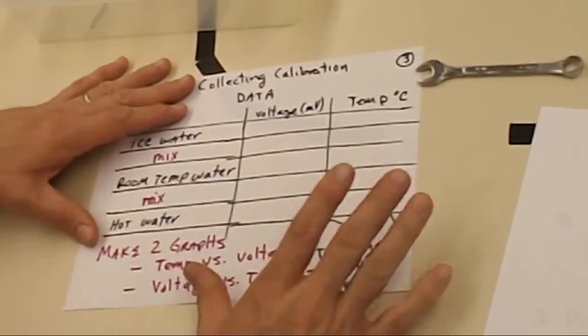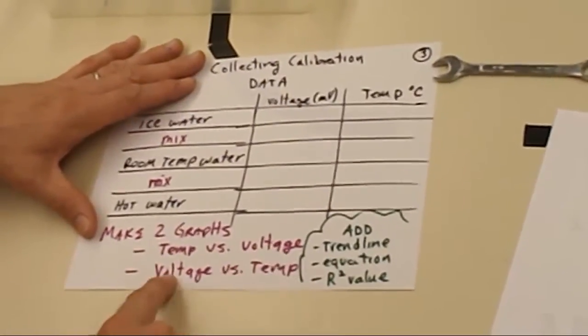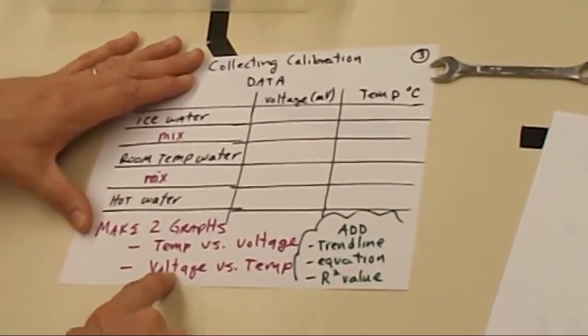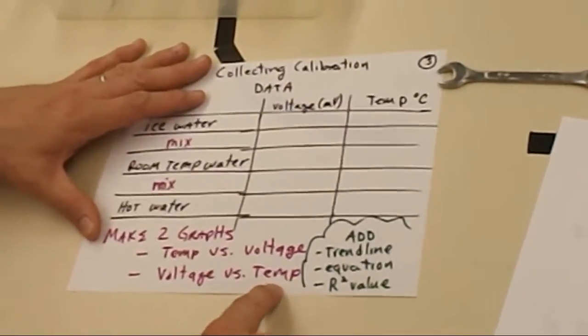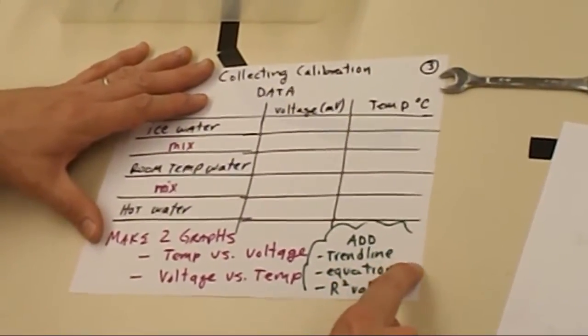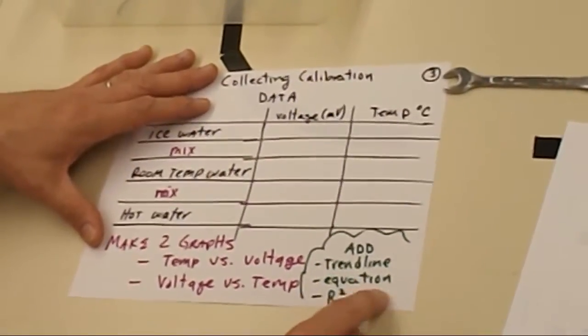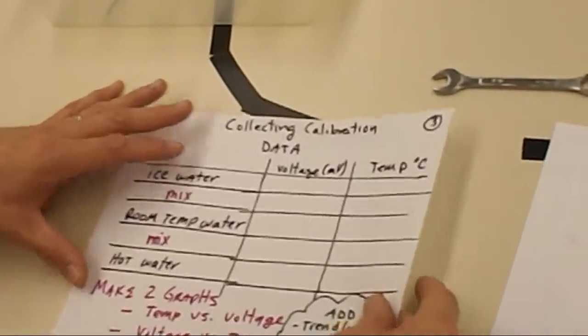What do you need to do once you have that data? You need to create two graphs. One of temperature versus voltage, and then one to flip it around and go voltage versus temperature. We're going to need to add trend lines to the data, include the equation and the R-squared value on the chart. So with that data, you can move on and complete the calibration.